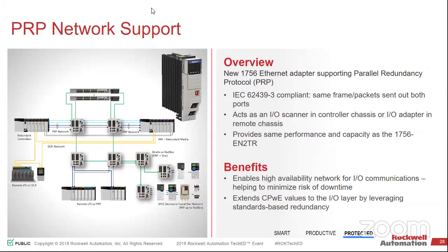Now, these are standard 5700 switches here? Yes. If you want to put a device that doesn't support PRP on it, there are some of the switches, the 5400s, that do support that protocol. And it's not a Rockwell specific protocol. Other people support the PRP protocols. Yeah, it's that IEC. If you see that numbering scheme, that 439-3, that's what gets called out in the specs, so that would be why we would go after it.